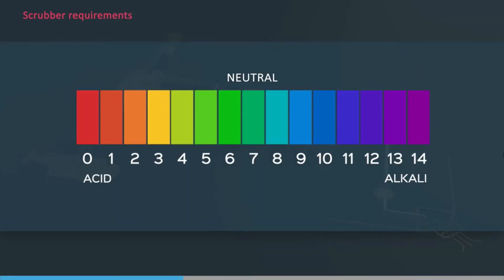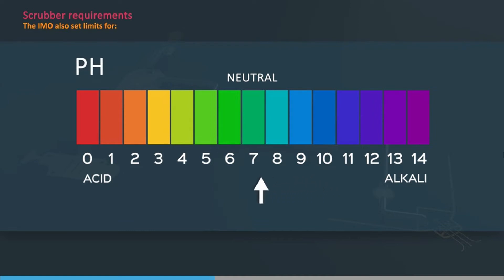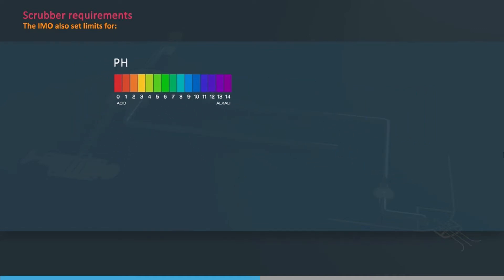To limit the environmental impact of any scrubber wash water discharges into the sea, the IMO also set limits for pH. The pH should not be less than 6.5 at the ship's discharge. When the ship is manoeuvring or in transit, a maximum difference between the wash water inlet and outlet of two pH units is allowed.